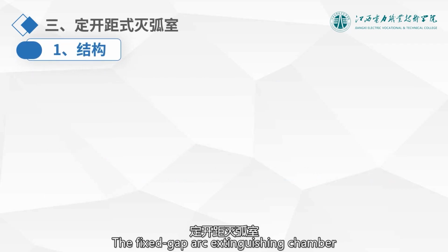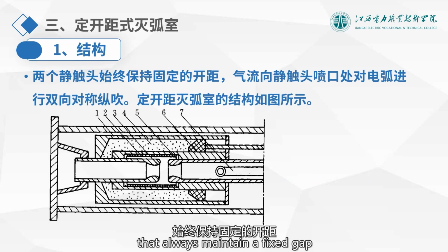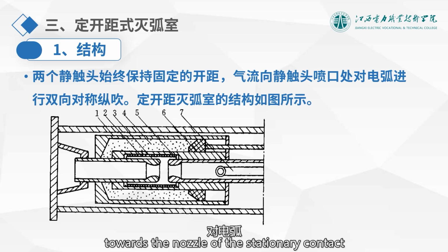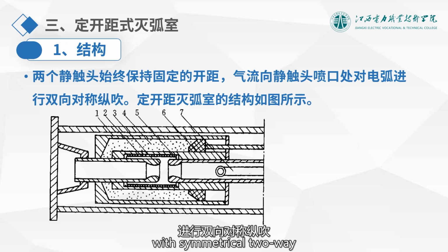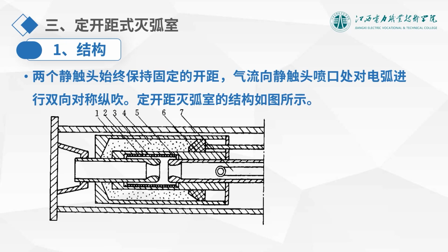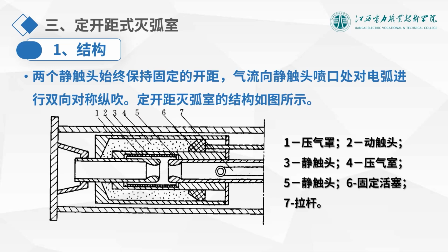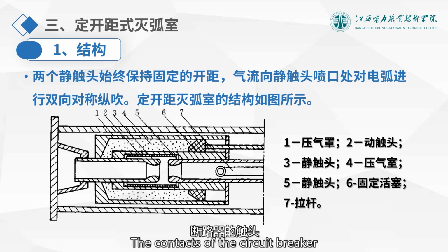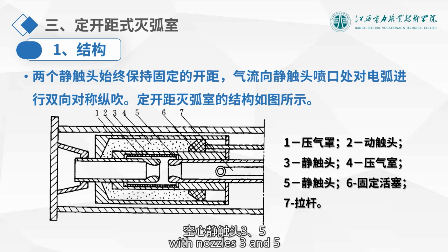The fixed gap arc extinguishing chamber has two stationary contacts that always maintain a fixed gap. The airflow blows the arc towards the nozzle of the stationary contact with symmetrical two-way longitudinal blowing. Its structure is as shown in the figure, and mainly consists of the contact, compression device, and pull rod. The contacts of the circuit breaker are composed of two hollow stationary contacts with nozzle 3 and 5, and a moving contact 2. When closing, the moving contact 2 bridges between the stationary contacts 3 and 5, forming the current path.